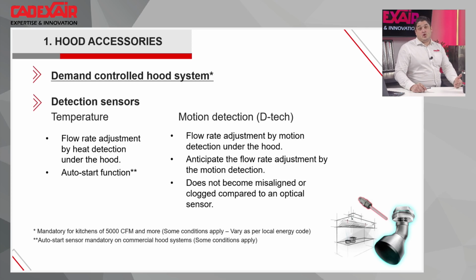So just to be sure, but in our case, we are around 3,000 CFM. It's not mandatory to put one. After that, it's a question of value and long-term operation. We will pay a little bit more to pay a little bit less in everyday operation. And also in some areas you could get a subsidy from the government or the gas company because you have a demand control system.